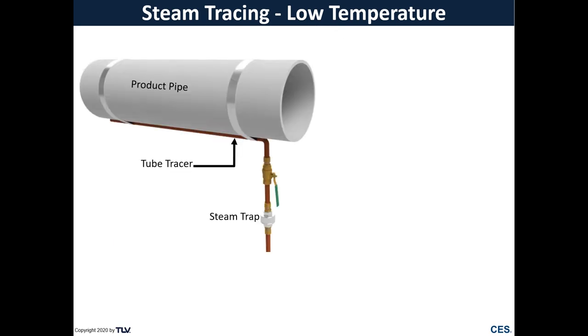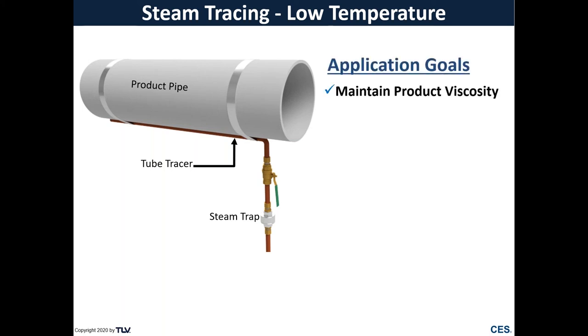So switching gears a little bit, getting into steam tracing. So steam tracing, for those who may not be familiar, we typically have a small diameter steel or copper tube that is attached to our steam system that is connected to the outside of a product pipe. And the goal of this steam tracer is basically to provide just a slight amount of heat to that product pipe in order to maintain product viscosity.